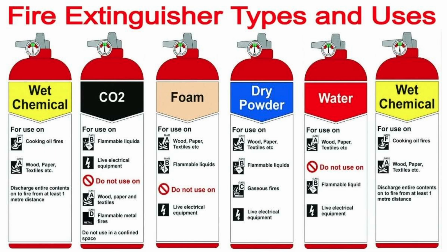C is current. An extinguisher with an ABC rating is suitable for use with fires involving ordinary combustibles, flammable liquids, and energized electrical equipment. So A is ordinary combustibles. An extinguisher that is rated for use with multiple hazards should include a symbol for each hazard type.